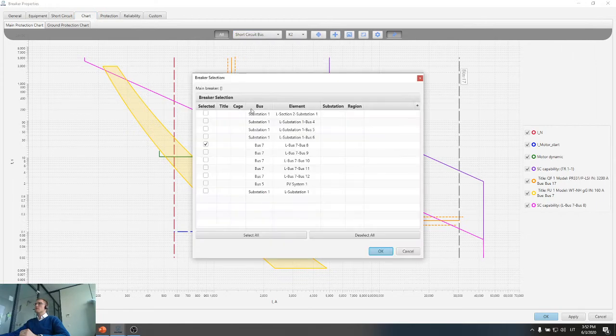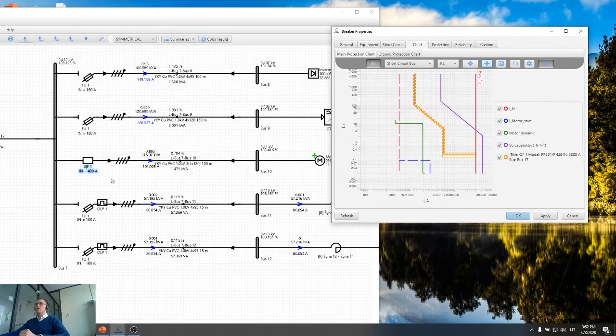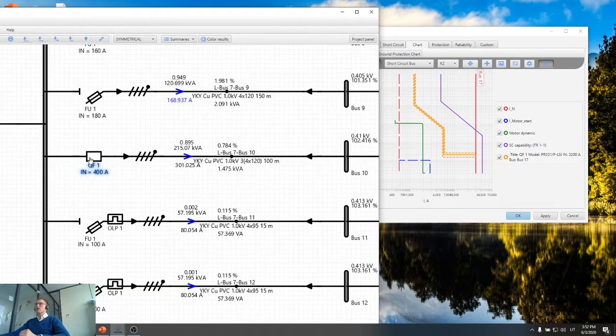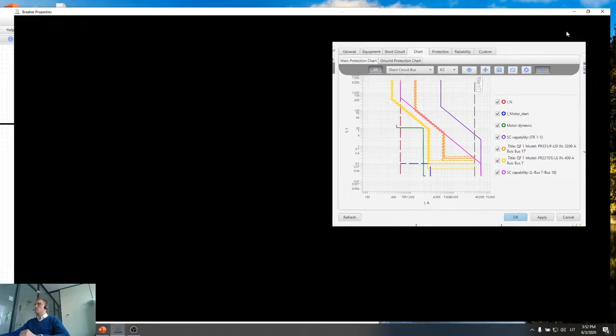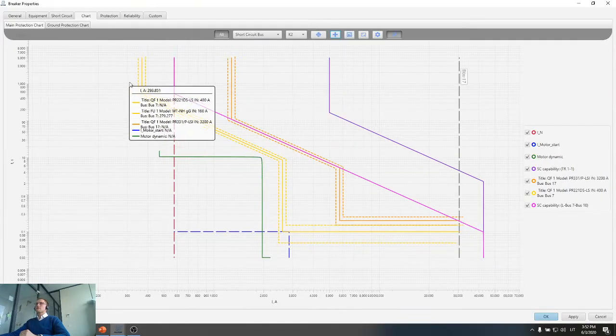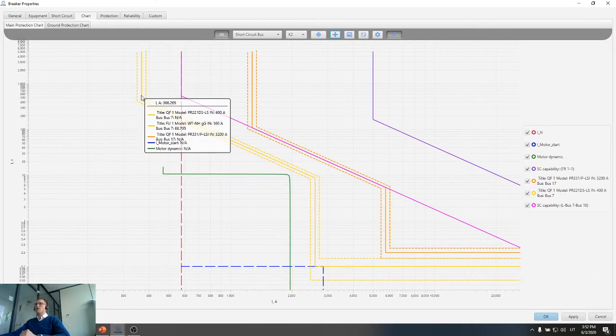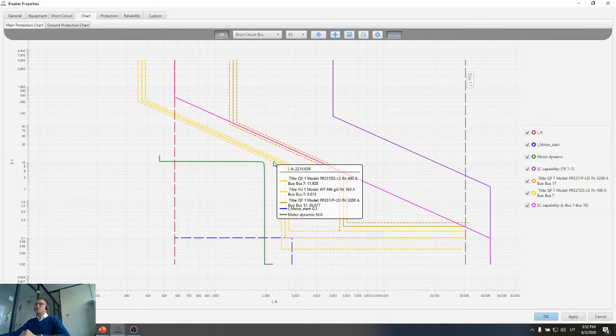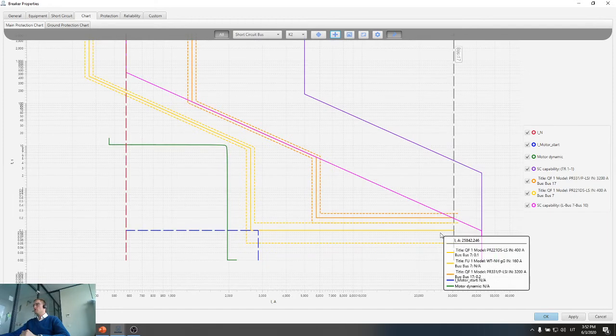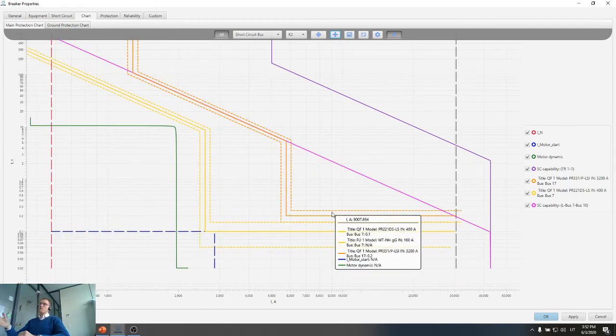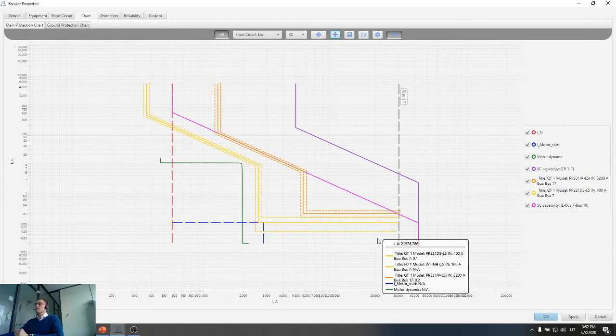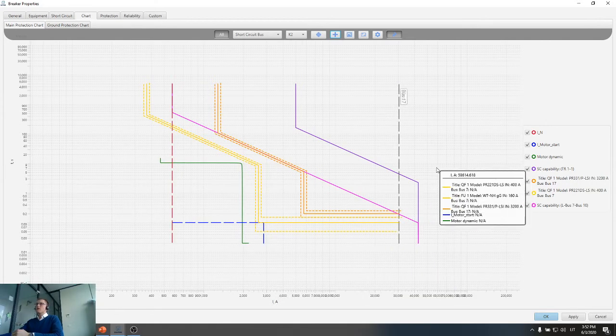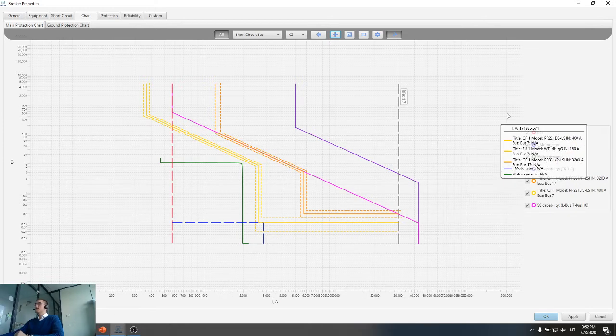Okay, now I will deselect the fuse and add this breaker here to make sure that my incomer breaker is selective with this breaker. I will put the breaker curve. Okay, so I can see that my motor breaker again has a lower pickup rating. It has a lower operation time, and in case of short circuit it also has a lower operation time. So my incomer breaker will wait for other breakers to operate, and in case those other breakers won't operate, then the incomer breaker will operate. So I believe that this kind of protection will work just fine. It is selective and with minimum time settings.